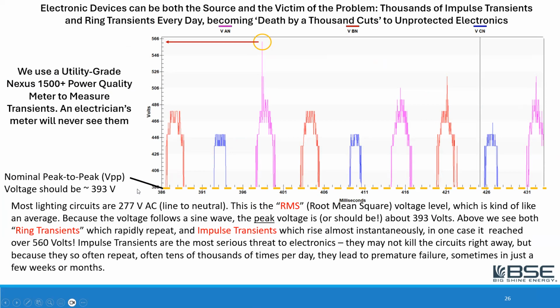So ironically, the electronics in our building are creating these disturbances in many respects, and they're also the victim of these disturbances. Because these impulse transients and ring transients happen almost constantly in many facilities, this becomes what we call death by 1,000 cuts, or maybe literally death by 1,000,000 cuts. The electronics can take it for a while, but over time, it can only be hit so many thousands or millions of times, and then eventually it blows a hole in a circuit somewhere, and then your equipment fails.